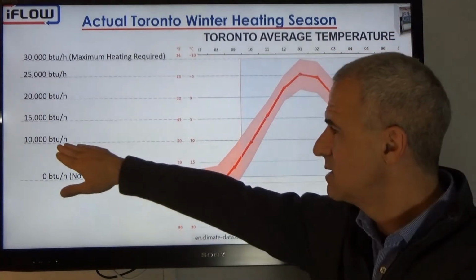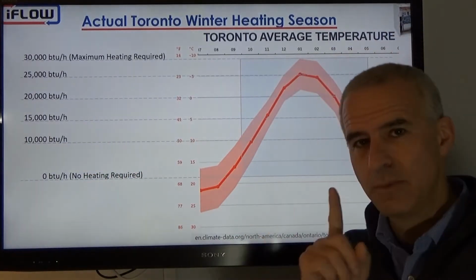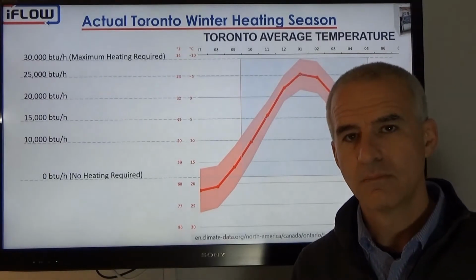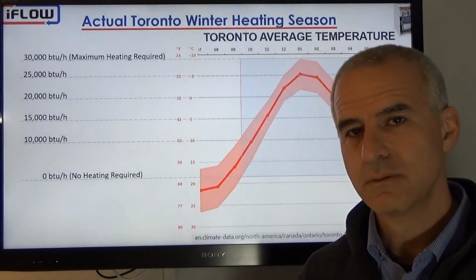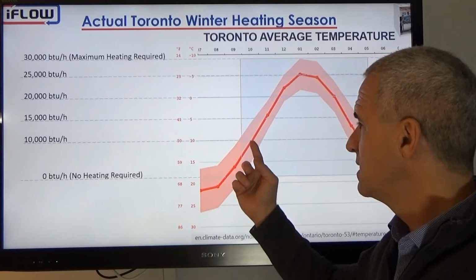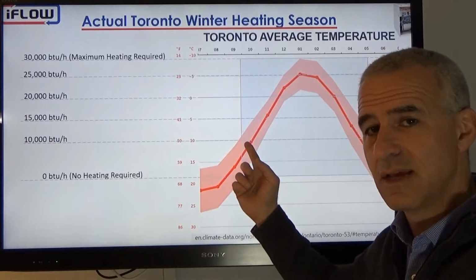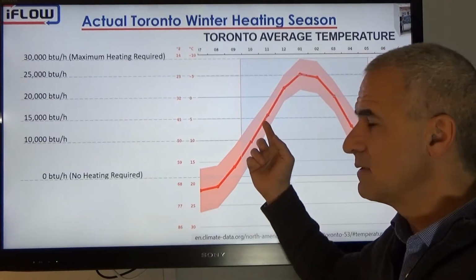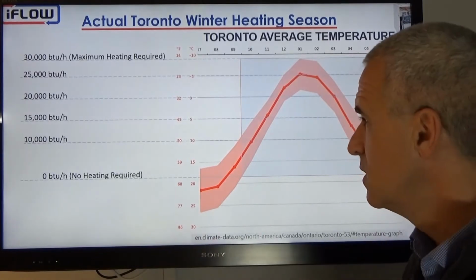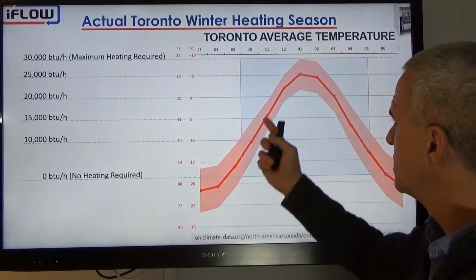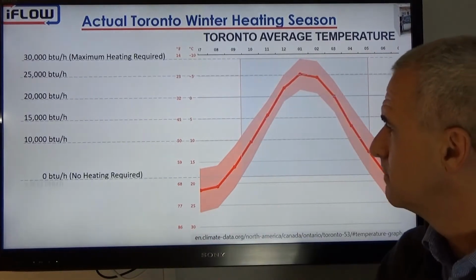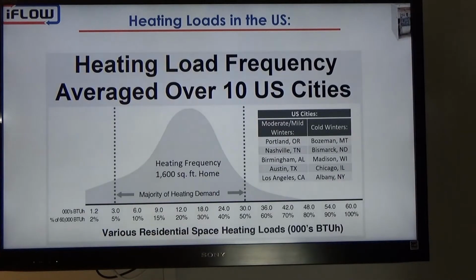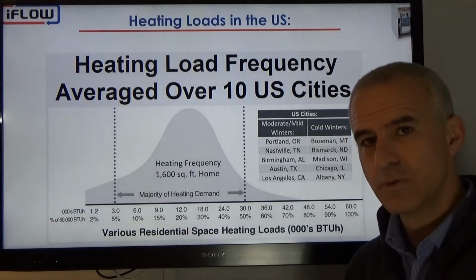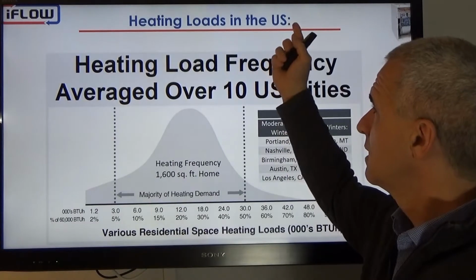And when you see this 10, 15, 20, think about the Navien A2 and think about those minimum inputs, right? When we can go down to 10,000 BTUs and not cycle at all, right? 15,000 BTUs, no problem. So this is why we're excited about this when we actually look at the performance of the heating side. So let's look at the US side now. Those were the Canadian numbers. Now let's look at the US side.